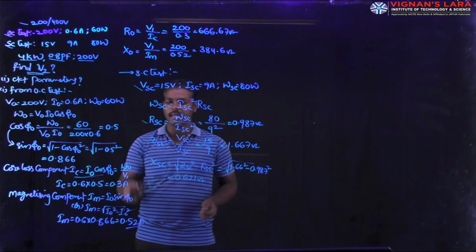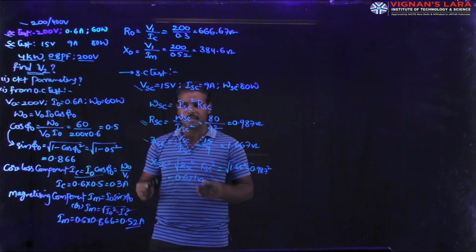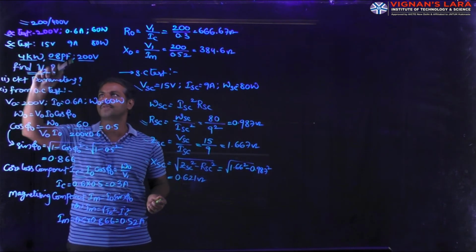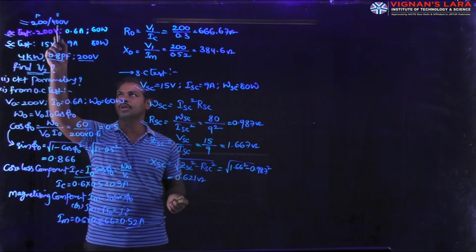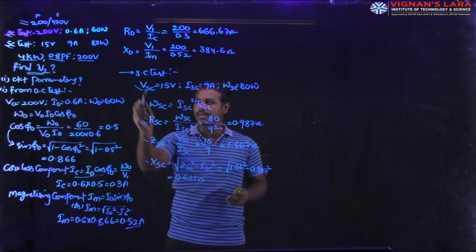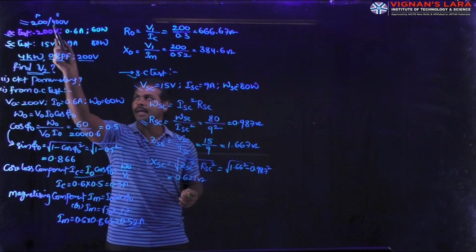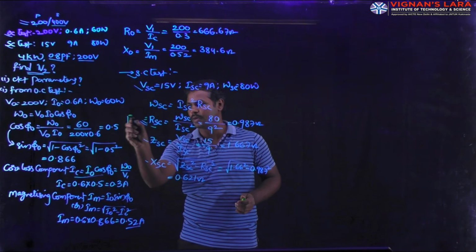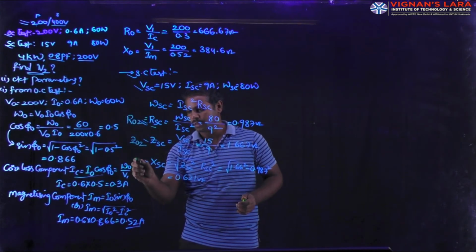So by using the short circuit test, we can find out the three parameters RSC, ZSC and XSC. In these equations, whether R01, X01 or R02, X02 is obtained is decided by the rating of the transformer. Here primary is 200 volts and secondary is 400 volts. The short circuit test is always conducted on the HV side, so high voltage exists on the secondary side, and we get R02, Z02 and X02.